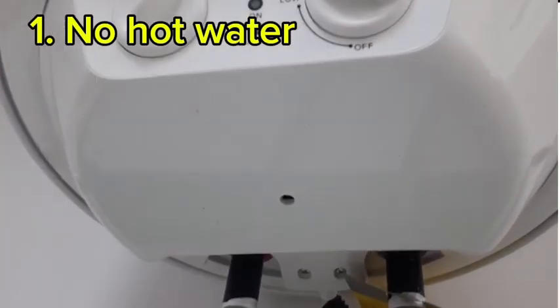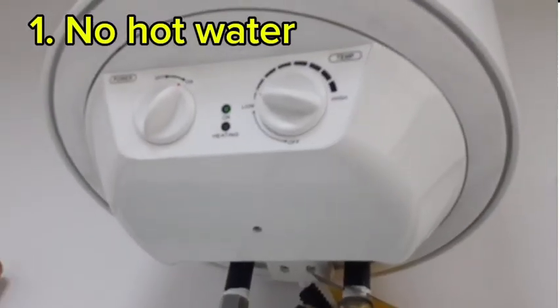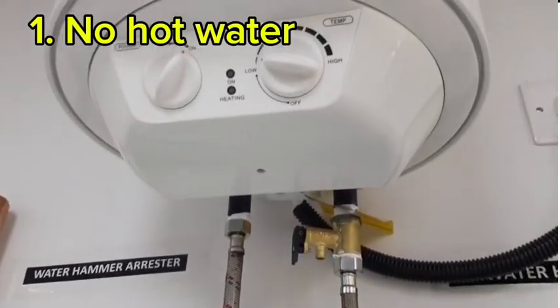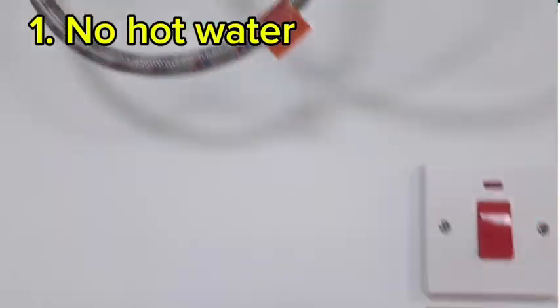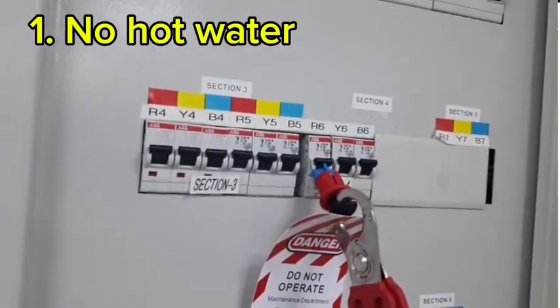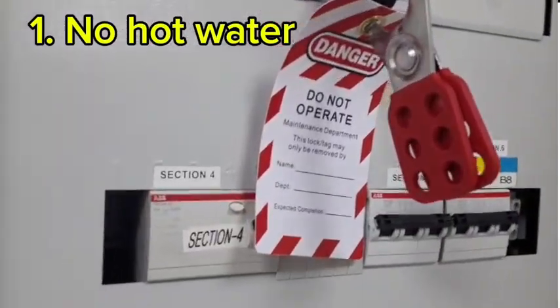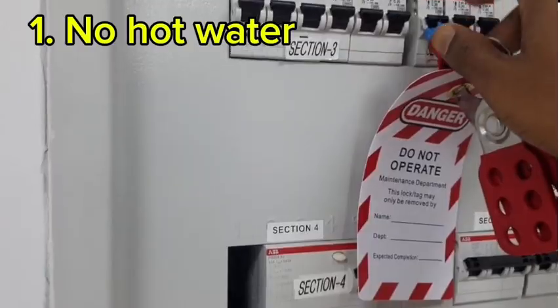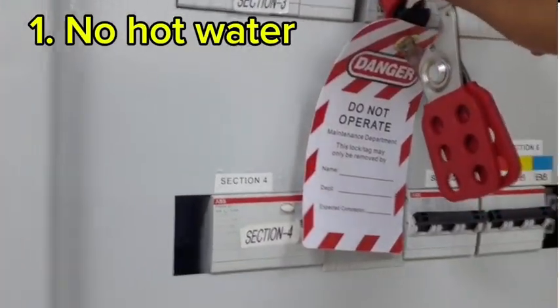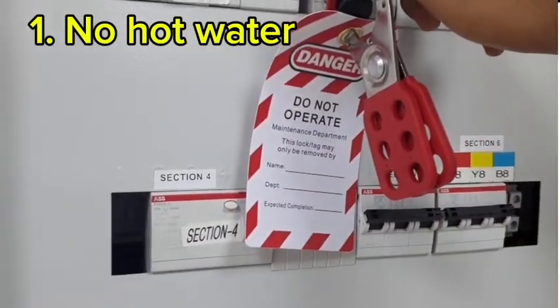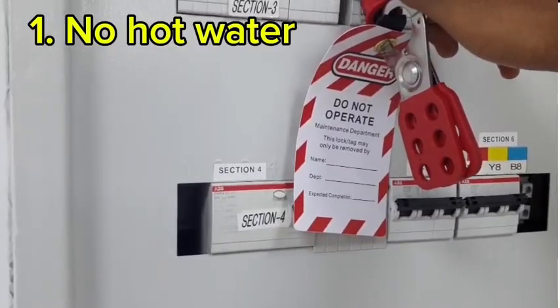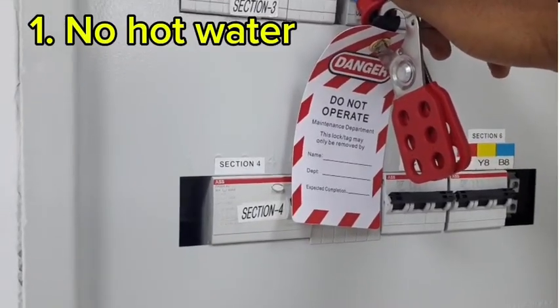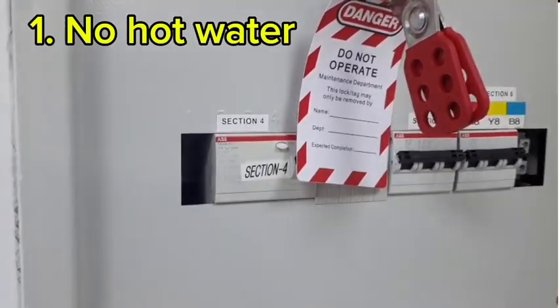So now we are going to open the cover to check the heating element. But before opening the cover, please make sure the power is off. In the electrical DB, the breaker has been switched off. The breaker should be switched off. Then lockout tagout should be provided. This is for safety, that means while you work with the water heater, no one can access the breaker to switch it on.